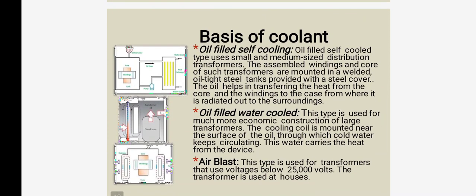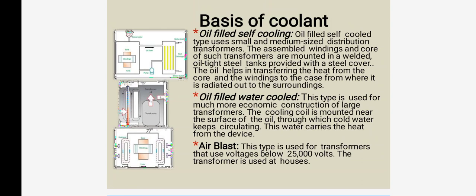So, basics of coolant. Oil filled self cooling. Oil filled self cooled type is used for small and medium sized distribution transformers. The assembled windings and core of such a transformer are mounted in a welded oil tight steel tank provided with a steel cover. The oil helps in transferring the heat from the core and the winding to the case, from where it is radiated out to the surroundings.